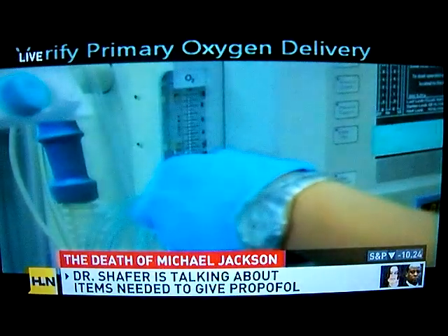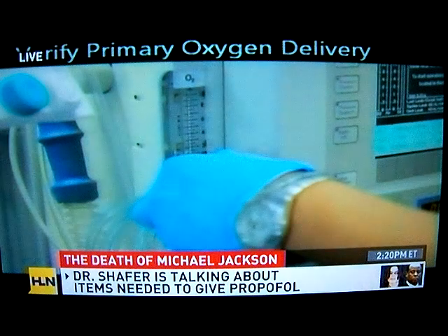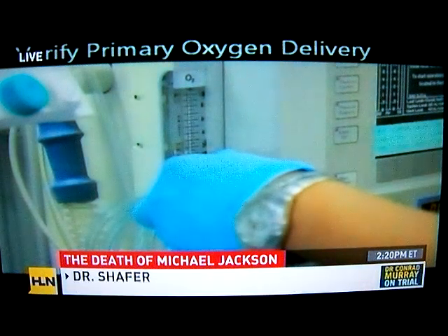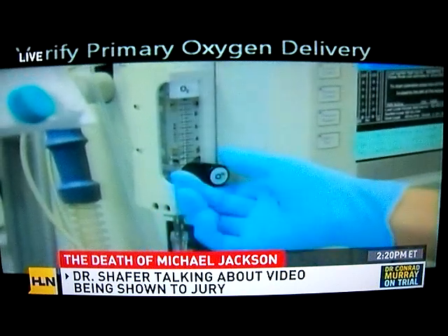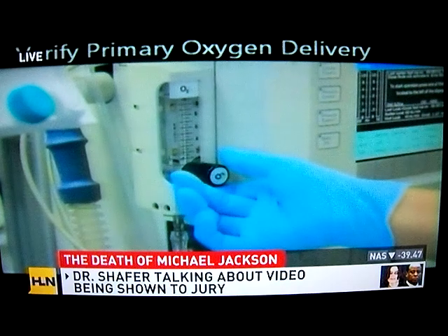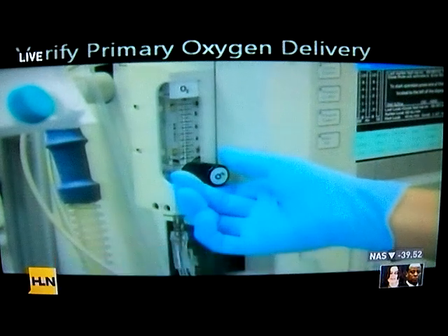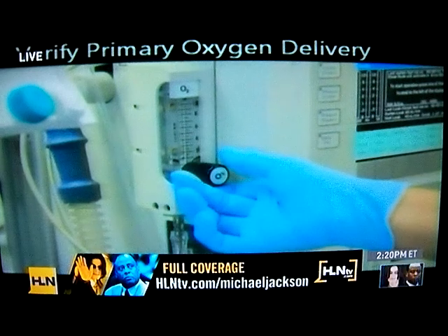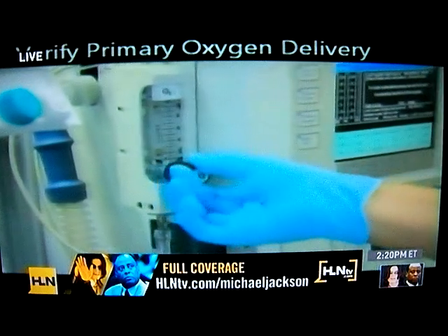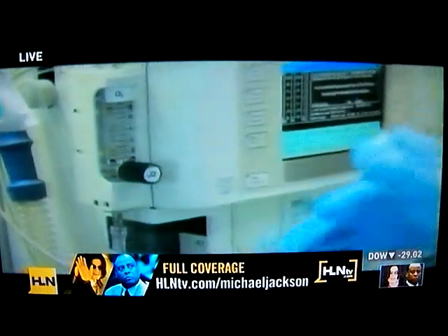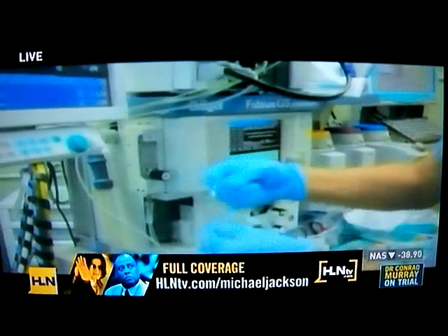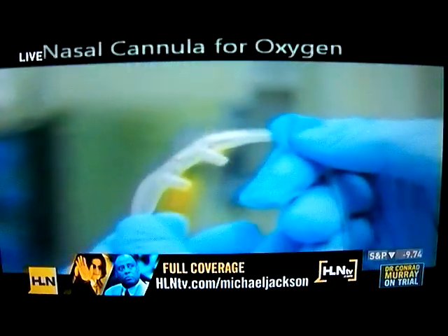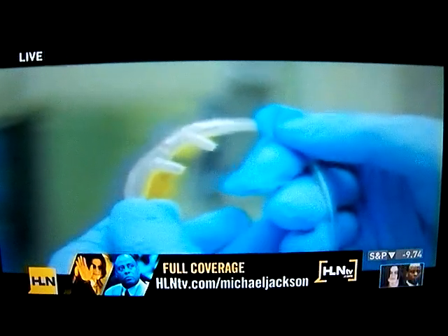The slide is verify primary oxygen delivery. Yes, thank you. So oxygen delivery is key. And we have multiple sources in the operating room of oxygen. This right here is oxygen for a sedation case that will come through nasal prongs. And what you do is you have to see that, is it hooked up? Does the plumbing work? The anesthesiologist is responsible to be sure that this works. So if you continue, please. So Dr. Hung here now opens it up and verifies that, yes, here's the tubing. Is oxygen coming out of this? That goes in the nose.